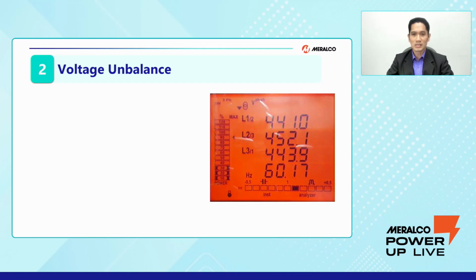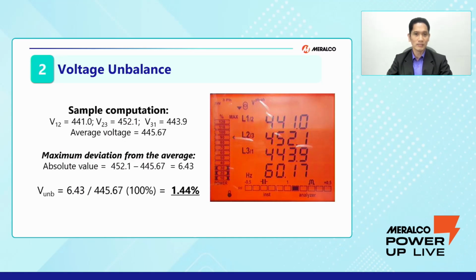For the example, for the voltage unbalance, we have here our voltage readings: for line 1 to 2, that is 441 volts, for line 2 to 3, that is 452.1 volts, and for line 3 to 1, that is 443.9 volts. So for computing the average voltage, it yields 445.67 volts. For finding the maximum deviation from the average, we have the voltage line 2 to 3, that is 452. We subtract the average voltage of 445.67 volts, which now results in 6.43 volts.